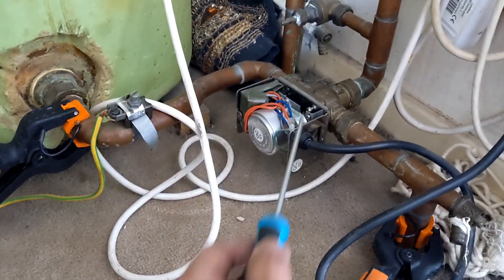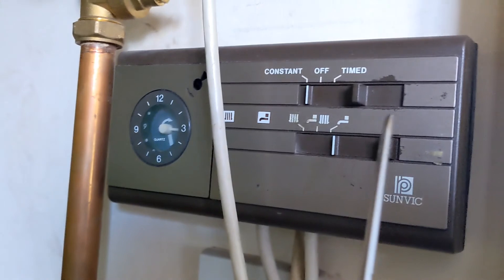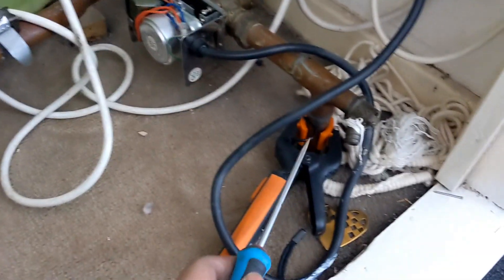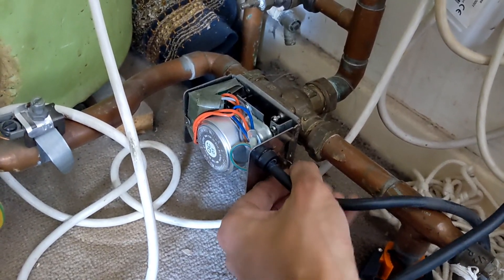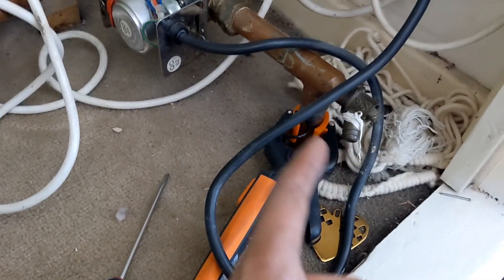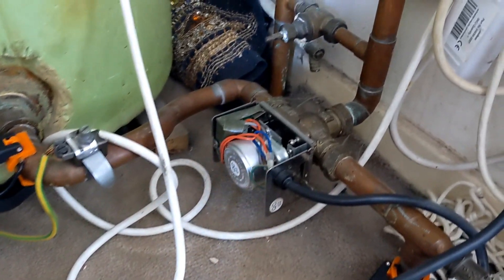Problem number two: the three-port is passing. Right now we've got it in hot water only mode and we've got heat going down the heating side anyway. Using the Testo temperature clamps — I'll put the screenshot up — there's heat passing down to the heating side even in the hot water position. So we're going to change the three-port over as well.